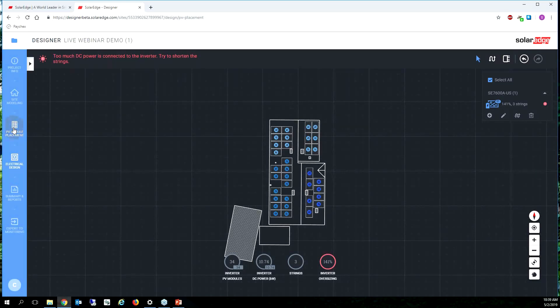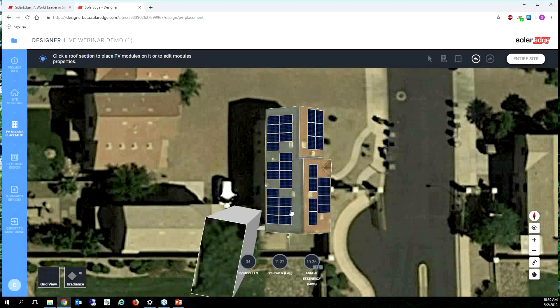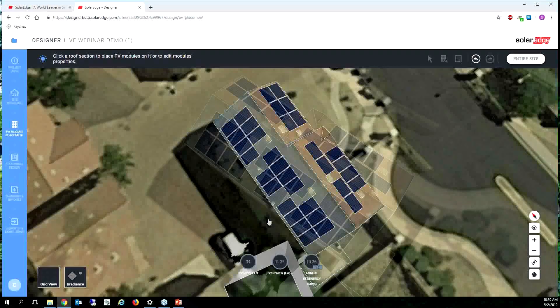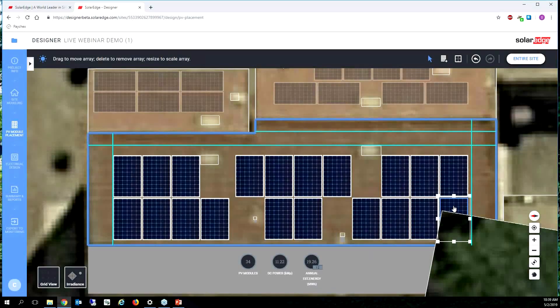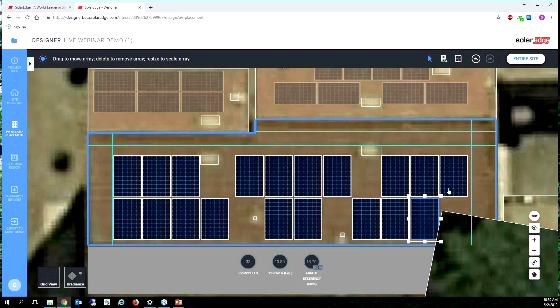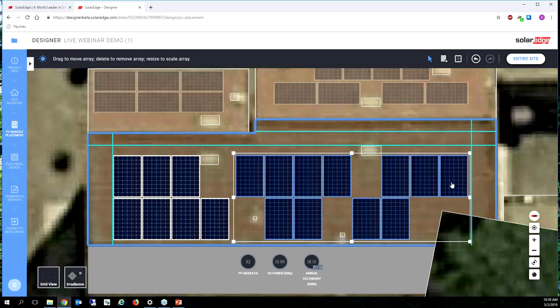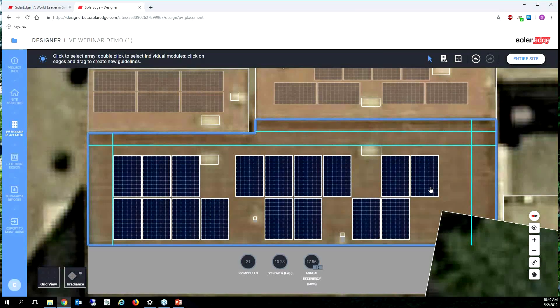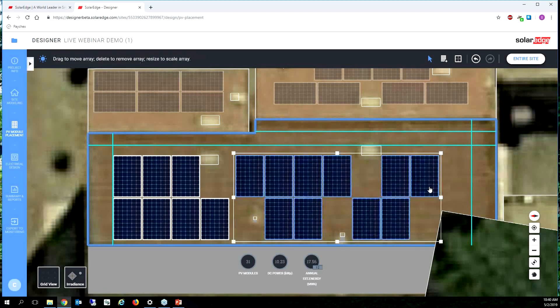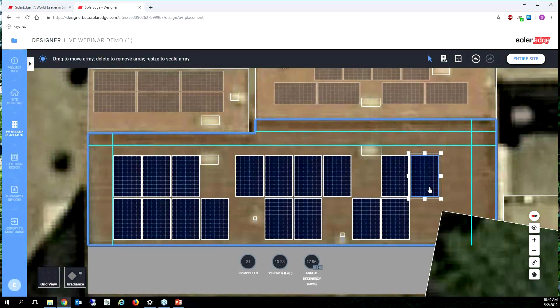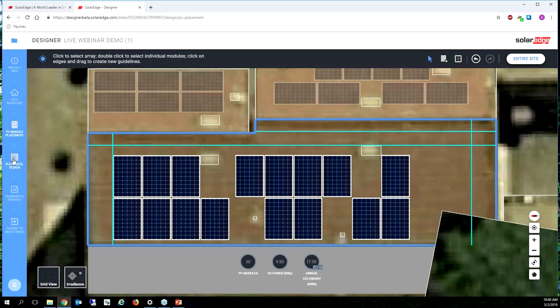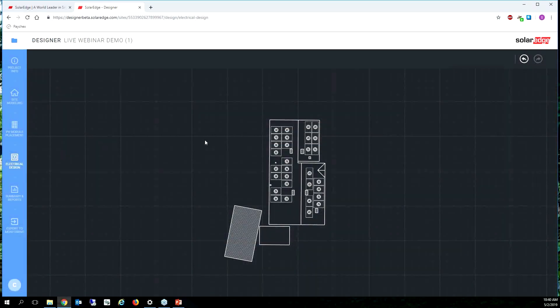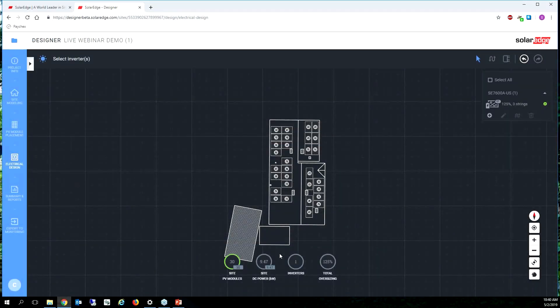So let's go back to our PV module placement and we know that these modules because of the shading, these modules are not ideal. So we're gonna delete maybe three of them, we'll delete four of them. We'll go back to electrical design. All right fantastic, my DC AC ratio is 125 percent now.